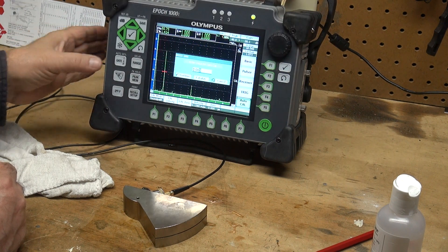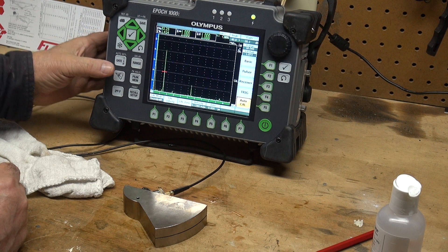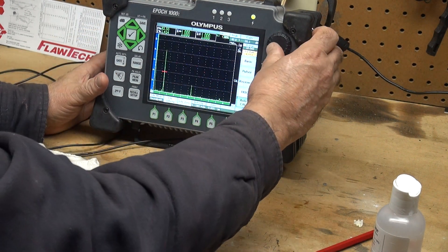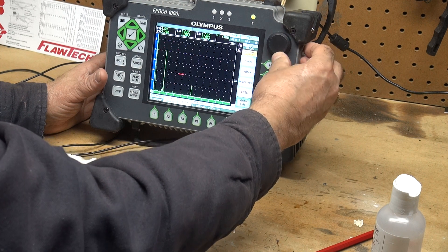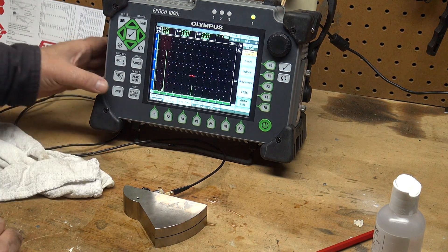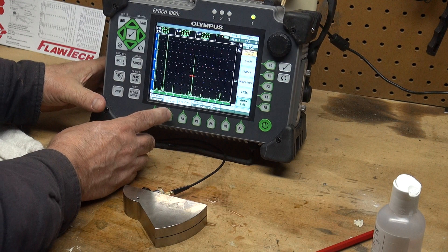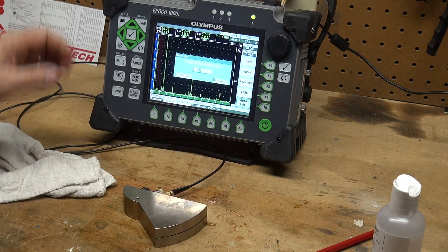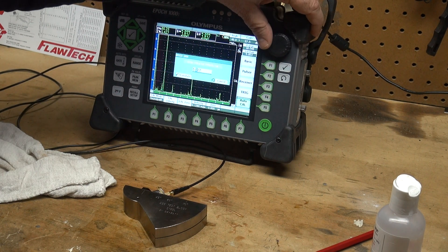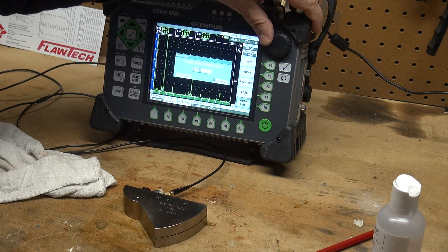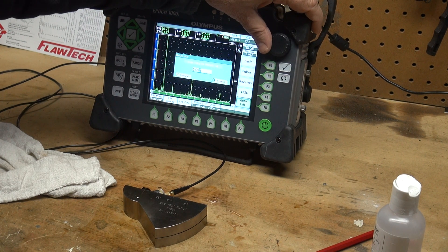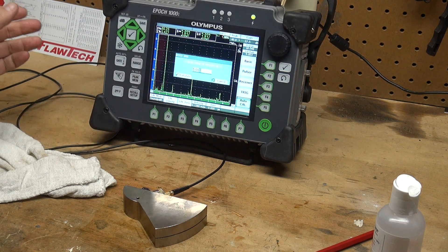All right, right there, hit the continue button. And then I can move my gate over and capture my five-inch radius, or I can capture the nine-inch radius, but I'm going to capture the five. Take that to 80 percent full screen height, do a cal velocity, and change this to a five-inch sound path, and then hit the check to calibrate.